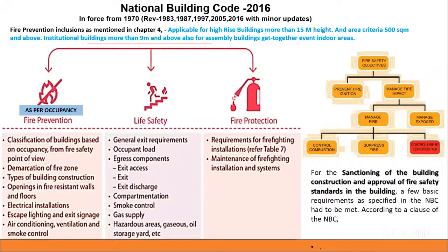The National Building Code has been enforced since the 1970s in India, with various revisions from 1983 till 2016, and minor updates still coming after various case studies. Fire prevention is covered in Chapter 4, applicable for high-rise buildings, which should be more than 15 meters in height with a floor plate of at least 500 square meters and above. This also applies to institutional buildings more than 9 meters, or assembly buildings where get-together events or indoor gatherings happen. It is divided into three parts: fire prevention, life safety, and fire protection laws.